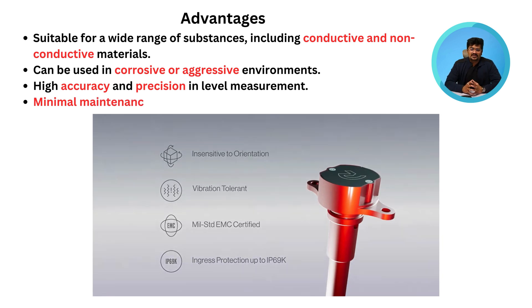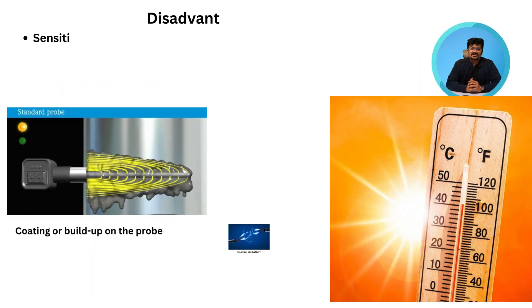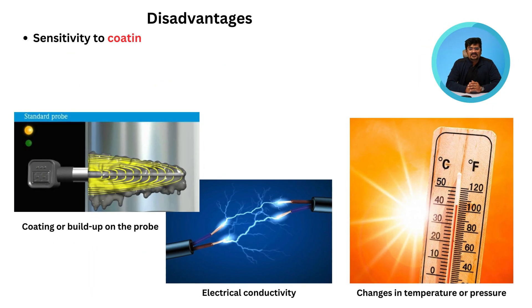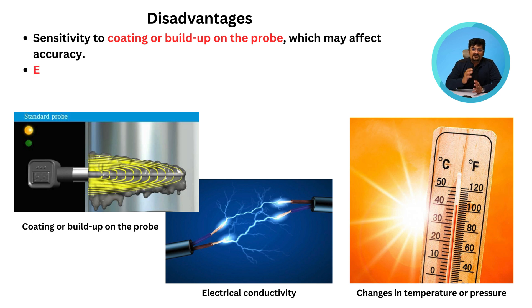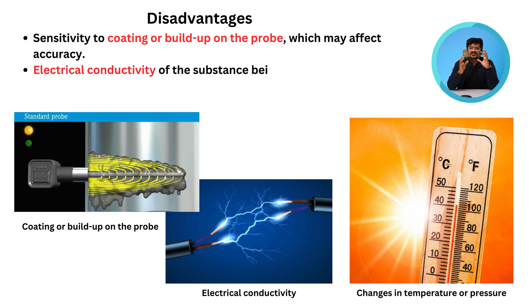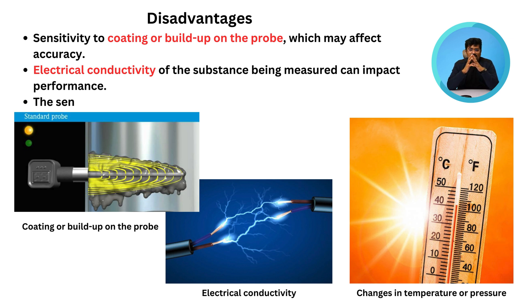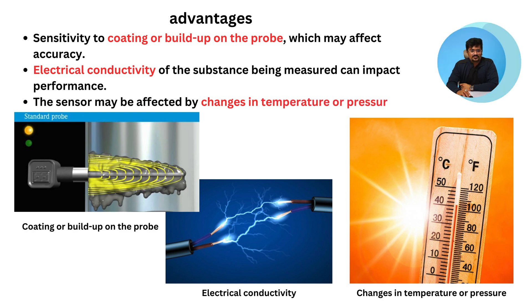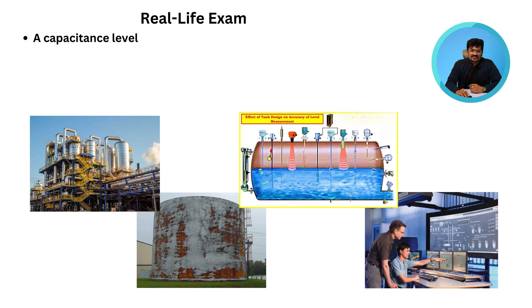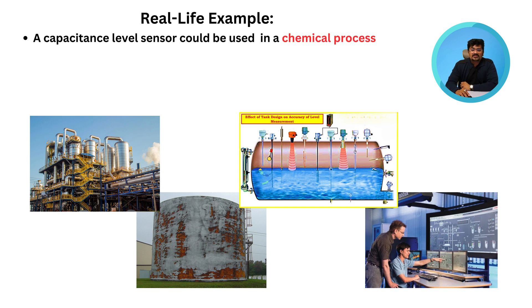Additional advantages include minimum maintenance required. Main disadvantages are sensitivity to coating or build-up on the probe, which may affect accuracy. The electrical conductivity of the substance being measured can impact the performance of the sensor. The sensor may also be affected by changes in temperature or pressure.